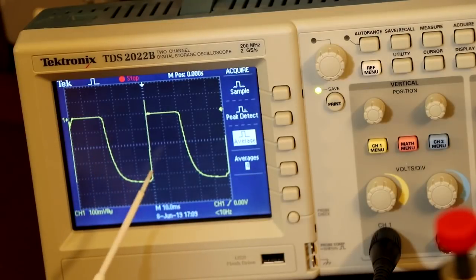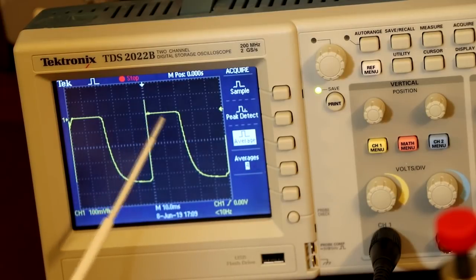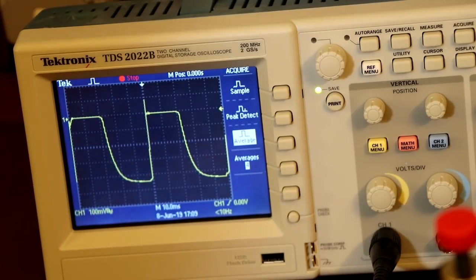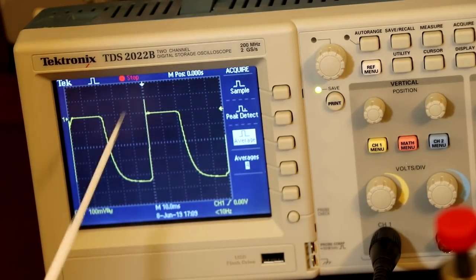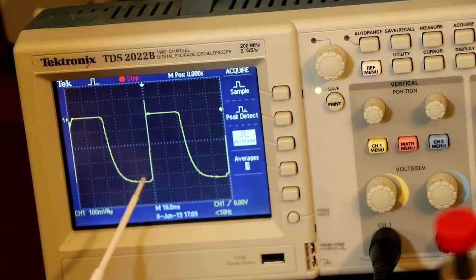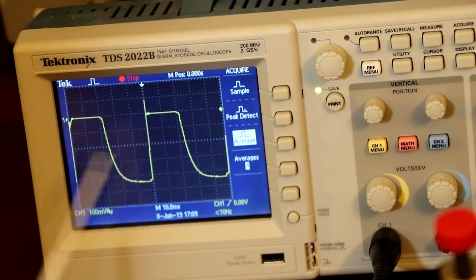So here's our current waveform, and it's about 450 millivolts, maybe just under, maybe 420 millivolts from the bottom to the top of the waveform there. If we look at the setting on our Hantek probe, that's on the 1 millivolt equals 10 milliamps range. So it's about just under 4.5 amps between the top and bottom of our waveform there.